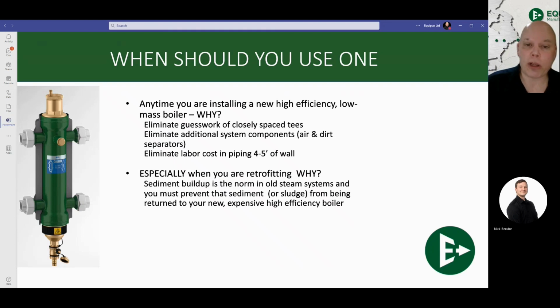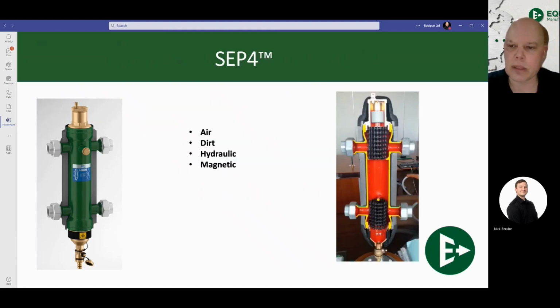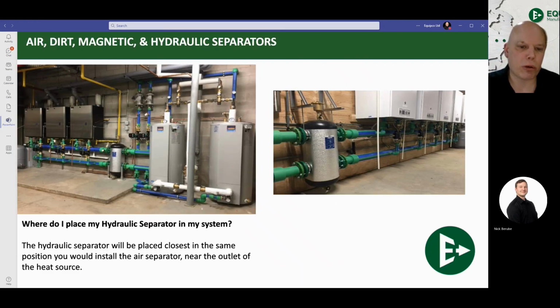You're going to be saving money on labor, on piping, and on additional pieces, because the one you're looking at has the high efficiency air, high efficiency dirt, and magnetic built into it all in one, so you don't have a multitude of pieces. And here's a little cutaway. You can see on the inside the coalescing media that creates that turbulence, making air pop out the top and dirt fall out of the bottom.